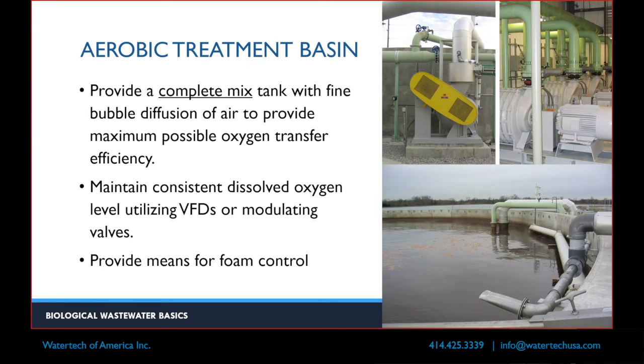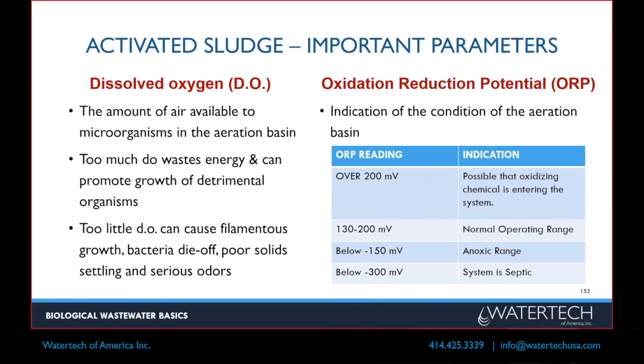So a lot of times we should have dissolved oxygen sensors so we can control dissolved oxygen, which helps make us more efficient with the amount of energy that we're using. And one of the big problems in wastewater plants, if they're not in control, is foam. So these are actually little spray nozzles that, if foam starts to develop, one way to control foam is to just spray on top of it and knock it down. So having some ability to control foam is pretty important.